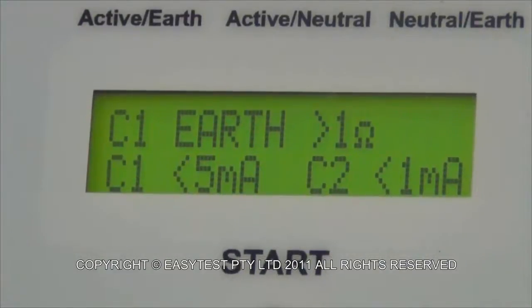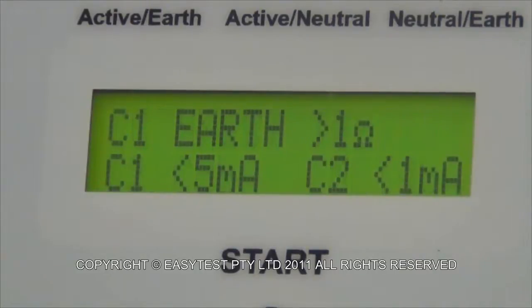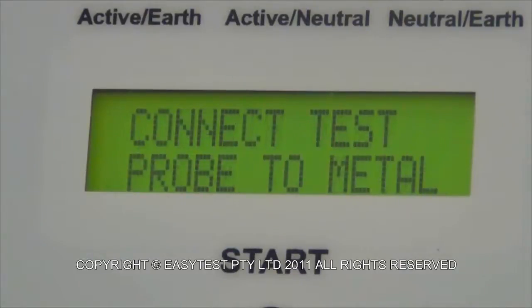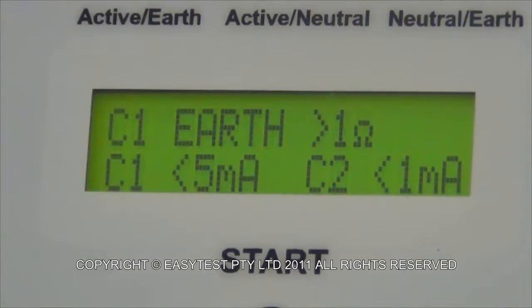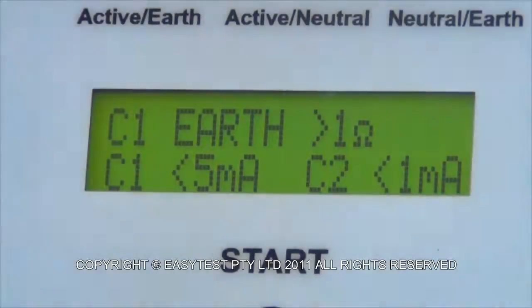You can see that now in its default condition. It says class 1 earth above 1 ohm, so it's a class 2 piece of equipment. You can ignore that. It says class 1 earth leakage less than 5 milliamps, class 2 earth leakage less than 1 milliamp. It's saying that because that is what it sees. Now, let's run the drill.